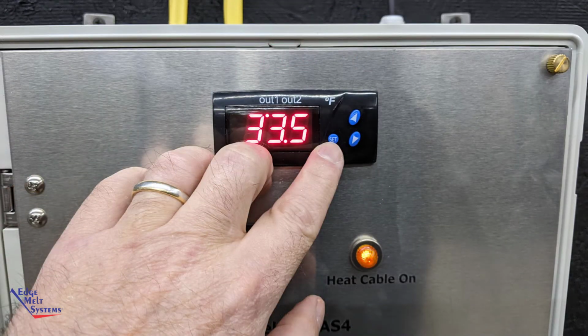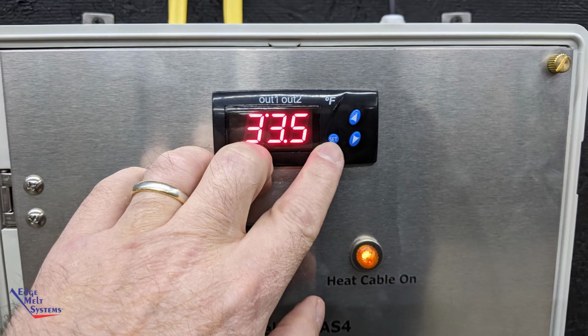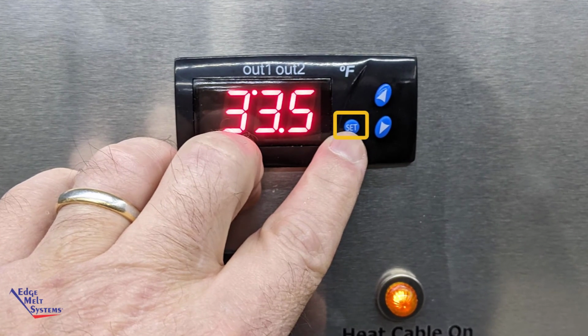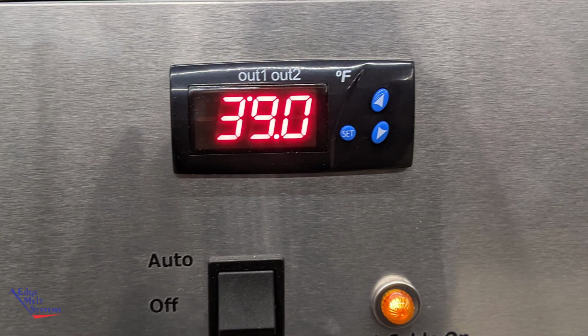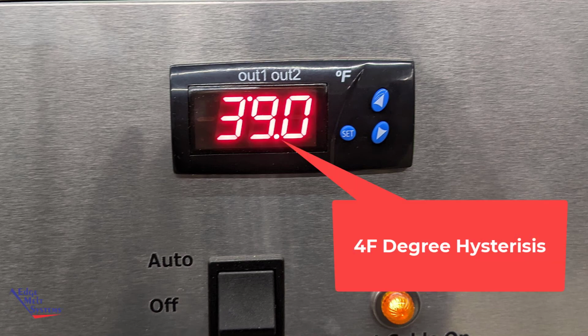To confirm the factory preset temperatures, as well as to make any adjustments to those temperatures, depress the set button once, and a temperature of 39 degrees Fahrenheit will begin flashing with a dot under the out one, indicating this is the first set value. To adjust up or down, use the arrows from there. There's a hysteresis built in to these temperature settings. So that's a temperature setting at which the heat cables will turn off when it rises above 39F. When it falls below 35F, the heat cables will be energized.